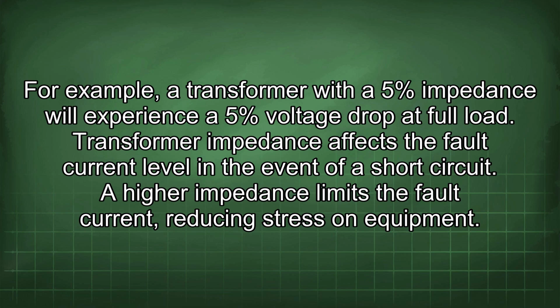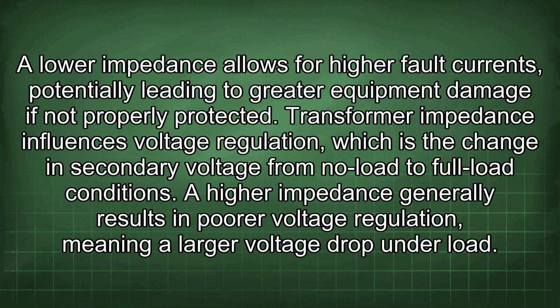Transformer impedance affects the fault current level in the event of a short circuit. A higher impedance limits the fault current, reducing stress on equipment. A lower impedance allows for higher fault currents, potentially leading to greater equipment damage if not properly protected. Transformer impedance influences voltage regulation, which is the change in secondary voltage from no load to full load conditions. A higher impedance generally results in poor voltage regulation, meaning a larger voltage drop under load.